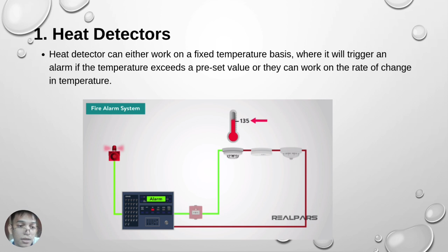The first is the heat detectors. Heat detectors can work on a fixed temperature basis, where they will trigger an alarm if the temperature exceeds a preset value, or they can work on the rate of change in temperature. It means if the temperature of the atmosphere around it decreases or exceeds the fixed temperature that is set into it, it will trigger.